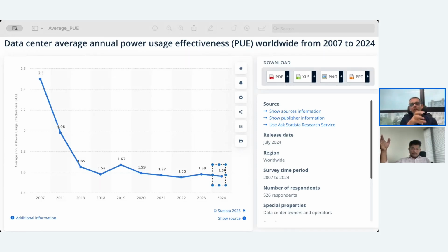To really get the cream of the benefit from improving PUE, level 3 measurement would be much better. You need to enhance your real-time monitoring systems to bring it to that level - rack level monitoring, or metering at the rack, PDUs, strips etc. of all your different IT equipment will be required.